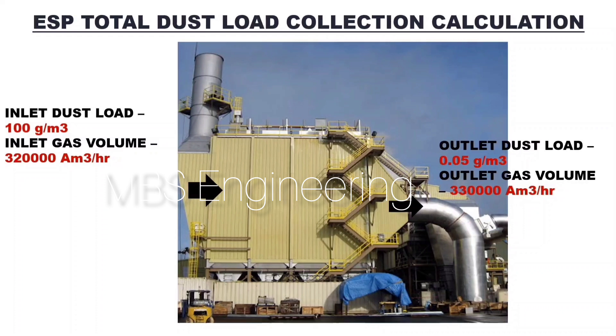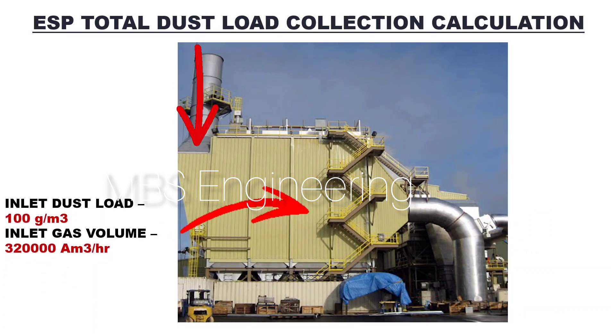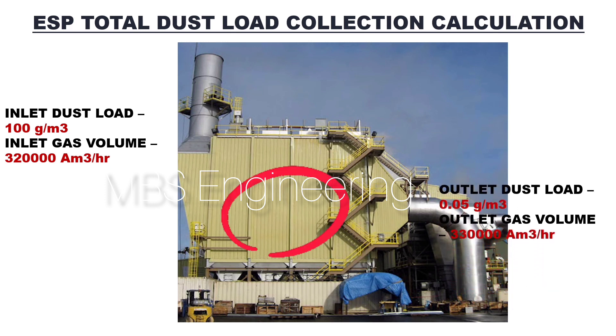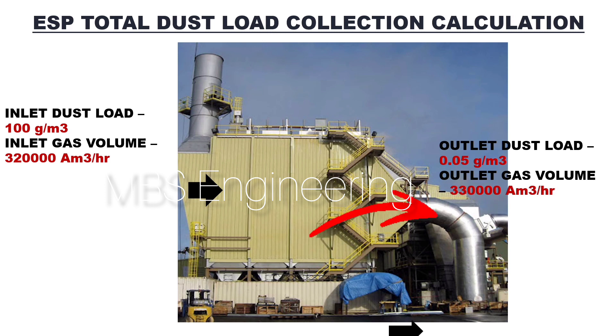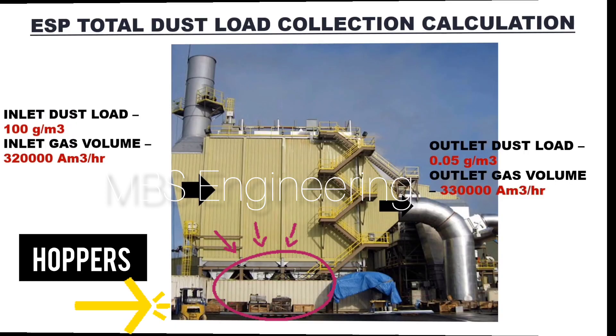Please refer to the ESP equipment schematic photos with the inlet and outlet duct connections. The gas flow through the ESP inlet has an inlet dust load concentration of 100 grams per cubic meter and an inlet gas volume of 3,20,000 cubic meters per hour. After sufficient dust collection takes place inside the precipitator, gas exits from the ESP outlet with a dust load concentration of 0.05 grams per cubic meter and an outlet gas volume of 3,30,000 cubic meters per hour. With the aid of the collecting and discharge electrodes, sufficient dust is collected in the hopper.